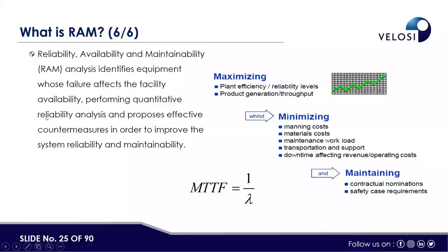From a RAM perspective, reliability, availability, and maintainability analysis identifies equipment whose failure affects the facility's availability and performance — specifically which parts of the machine or facility contribute more to downtime. By focusing on weak links and bad actors — components with higher failure rates or low MTBF — we can change their design, improve spares, or do more proactive condition monitoring. In this way we can increase the uptime or reliability of the plant.